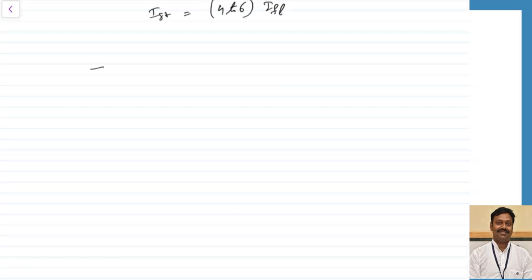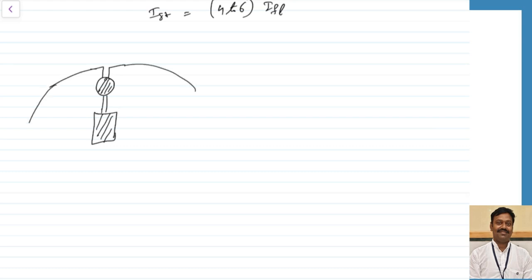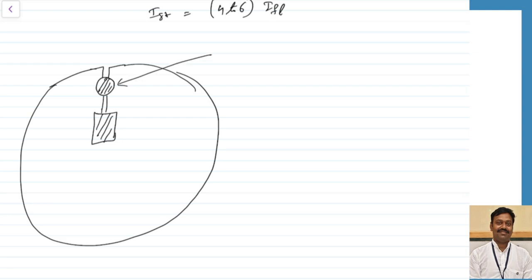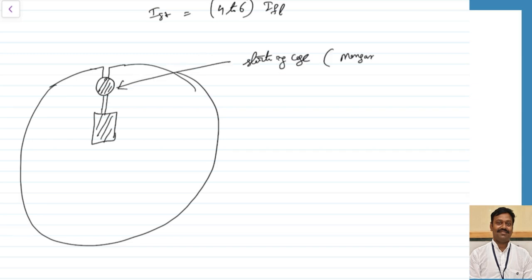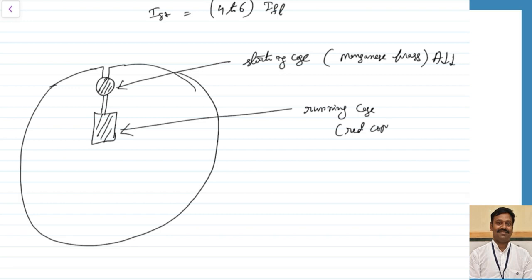The construction of the double cage induction motor is as follows. In the rotor, a bar is inserted on the outer side — this is the starting cage. Inside the notch, there is one more bar forming the inner cage. The starting cage is made up of manganese brass and has a very small cross-sectional area, giving it high resistance. The inner side is called the running cage, made up of red copper with a larger area so that resistance is less. Thus, the outer cage has more resistance and the inner cage has less resistance. An air gap is maintained in between the two cages.